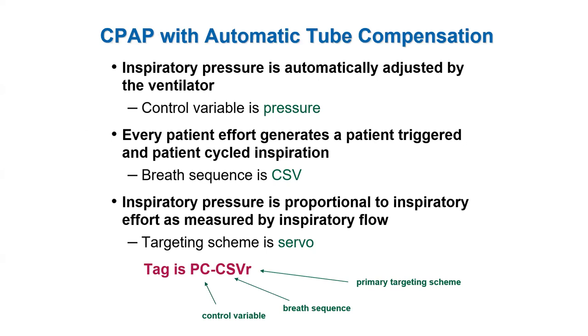Here is an example of a CSV mode. In this example, automatic tube compensation is added to CPAP to create a mode using the servo targeting scheme. As it turns out, both NAVA and PAV have the same tag, PC-CSVr. They're just different varieties of this category in the same way you can have different varieties of roses under the same species.